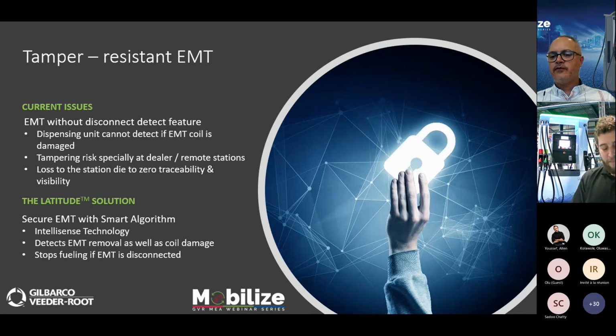In the past, people have manipulated these totalizers, either unplugging them or messing with the electromagnetic mechanism. So what have we done? First, if there's a disconnect with that particular electronic totalizer on a nozzle, the pump goes into an error state. Second, we have a kind of health check on the magnetic coil: every time a pulse is sent through it, we check if that electromagnetic totalizer is actually energizing. It's a twofold monitoring system for the EMT.